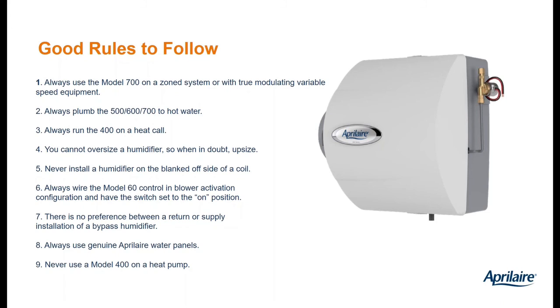You can't oversize the humidifier because it's always going to be turned off by the humidistat. So if you're not sure how tight the house is, upsize. When you're looking to cut your opening into the ductwork, if you're going to install it on the supply, make sure that you're not installing it on the blanked off A-coil side. So if you can see the fins and tubes, that's awesome. If you can see the blanked off side of the A-coil, you're not going to get good airflow.